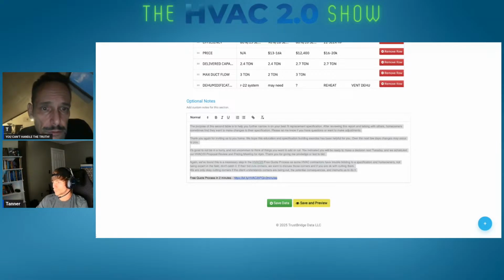If your new equipment is too large for your ductwork and static pressure is running outside of manufacturer's specification, warranty coverage for related failures may be voided. And then the 70-second video on duct pressure so they can review it again. And then building your specification report.